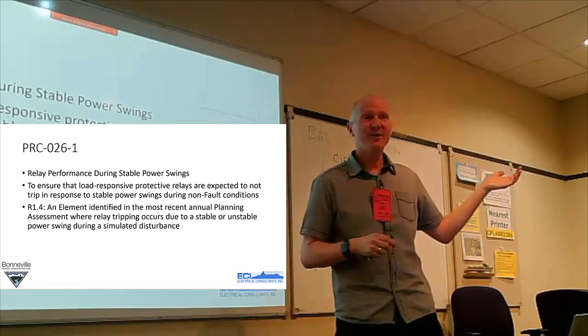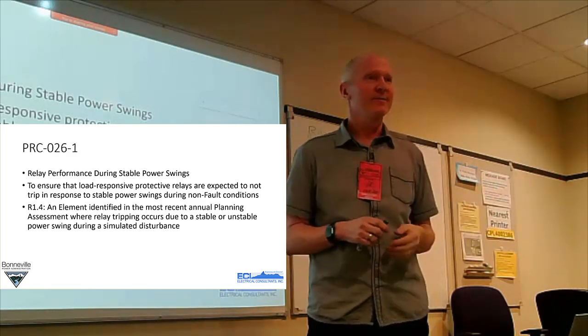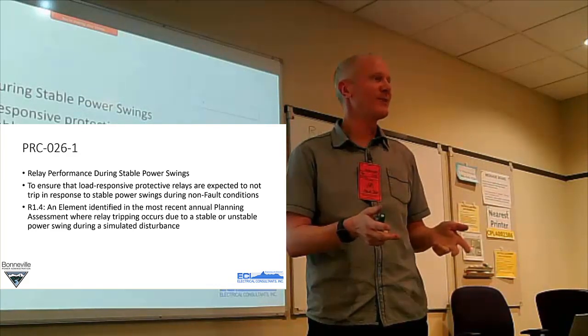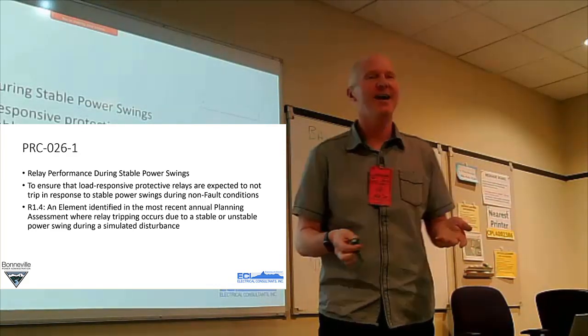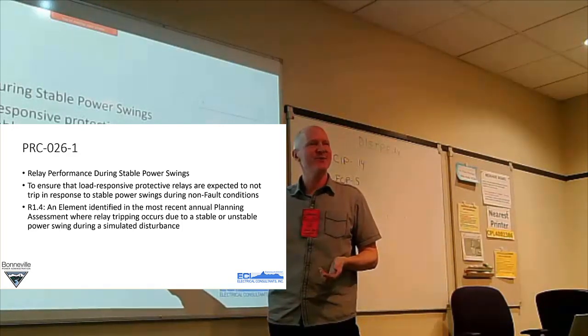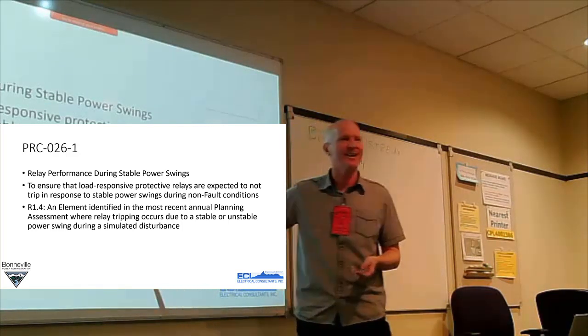It's a pretty fully functioning zone distance relay. You can set zone A, zone B, transfer trip. You can change the shape of the mho curve. It's stunning how well this works. And I look at this because they're assuming a lot. FERC and NERC, I think they're giving us all the credit we do not currently deserve, because nobody's modeling relays.